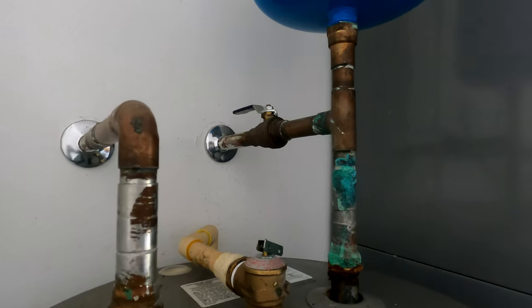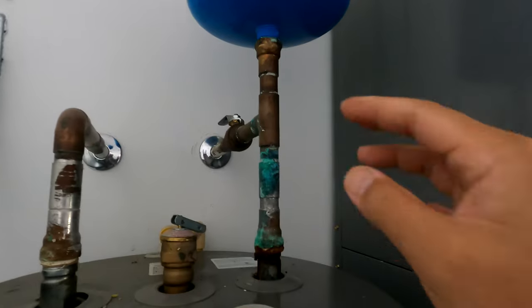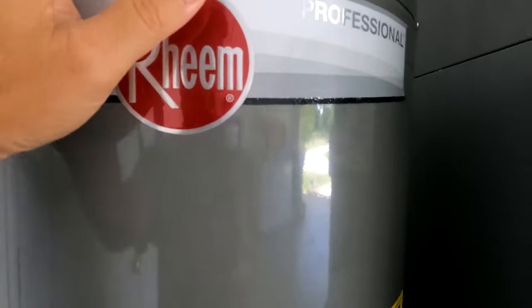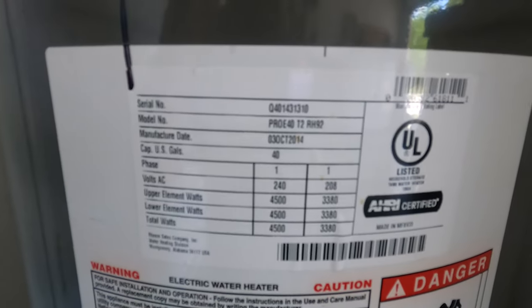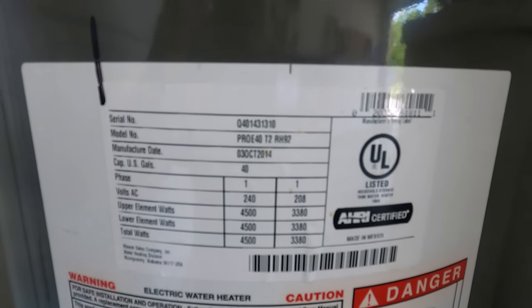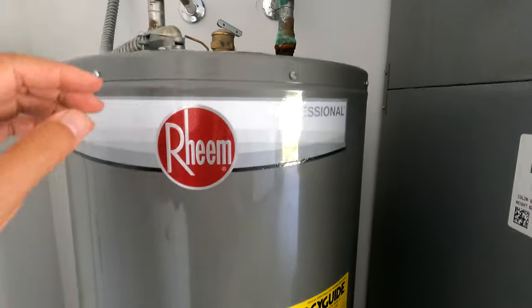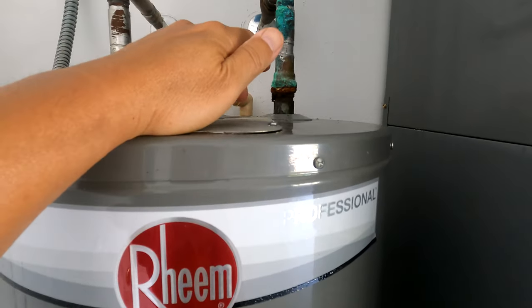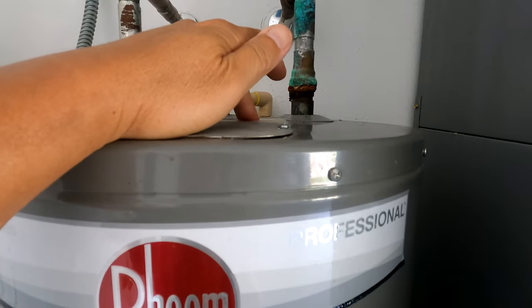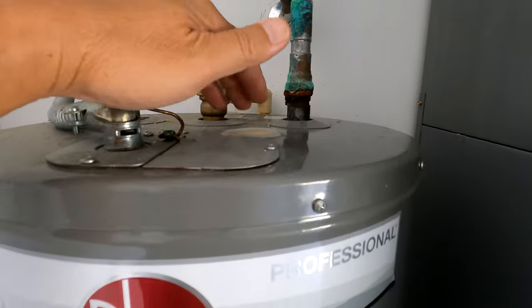From a different angle you can also see there's an expansion tank up here. This tank is about nine years old — it was manufactured in October of 2014. I'm suspecting that the anode rod in this tank has all dissipated with the mineral buildup.